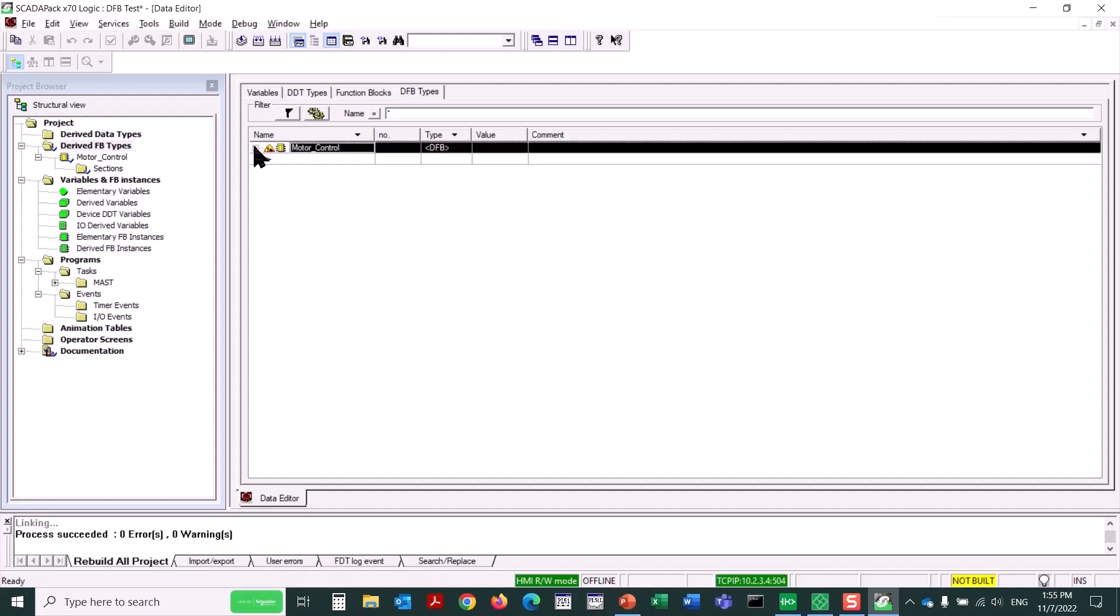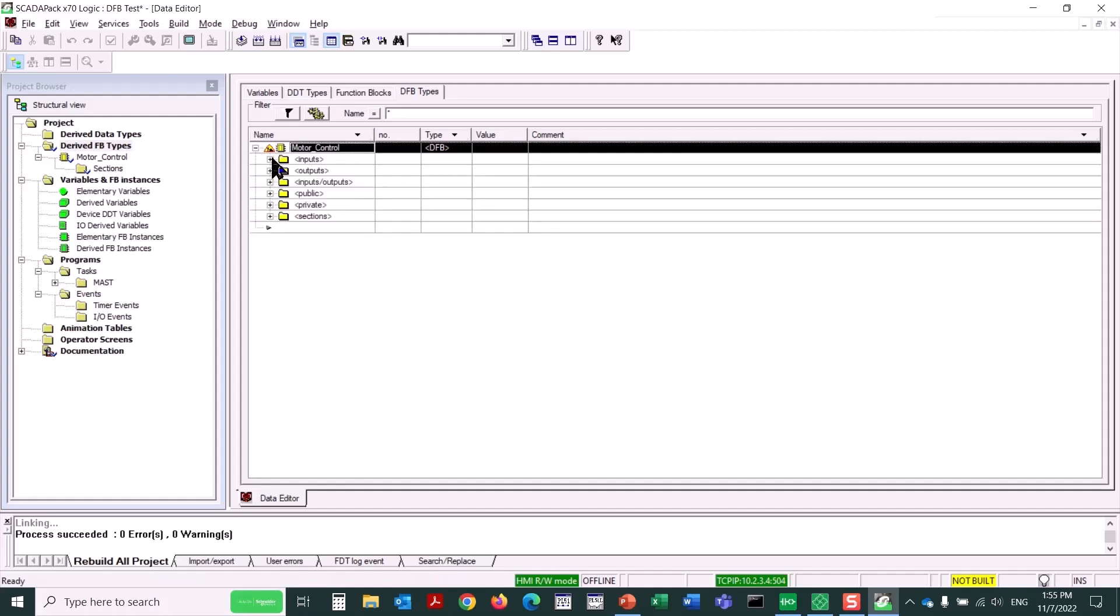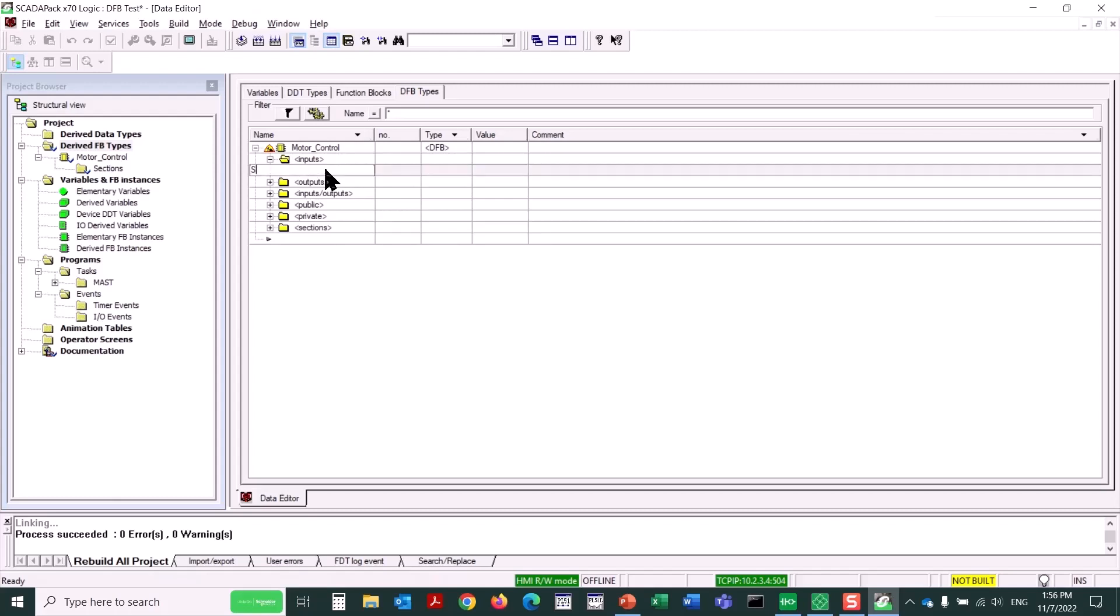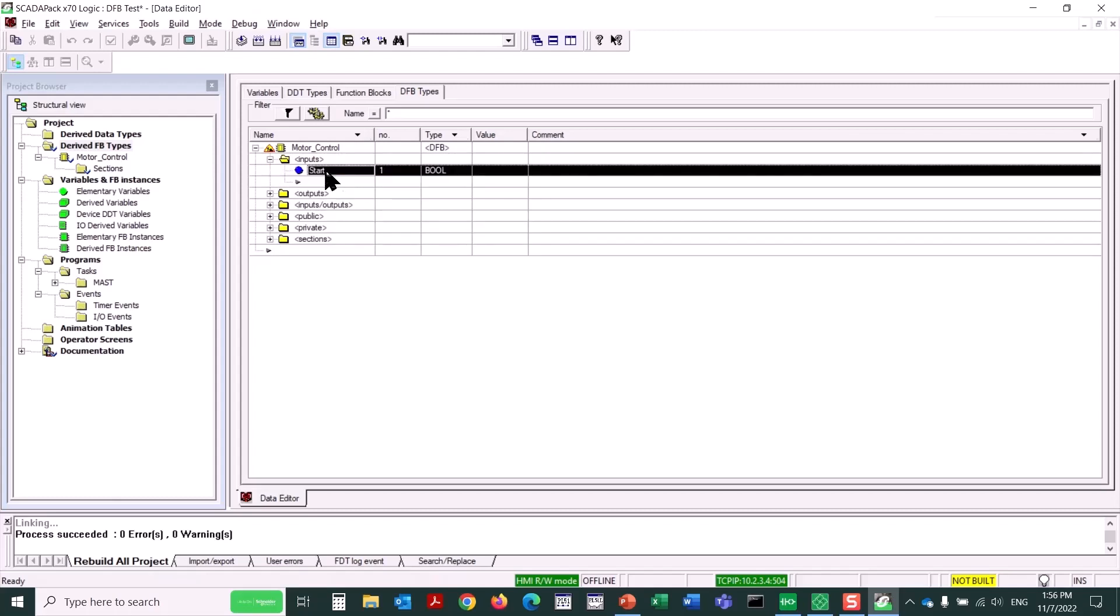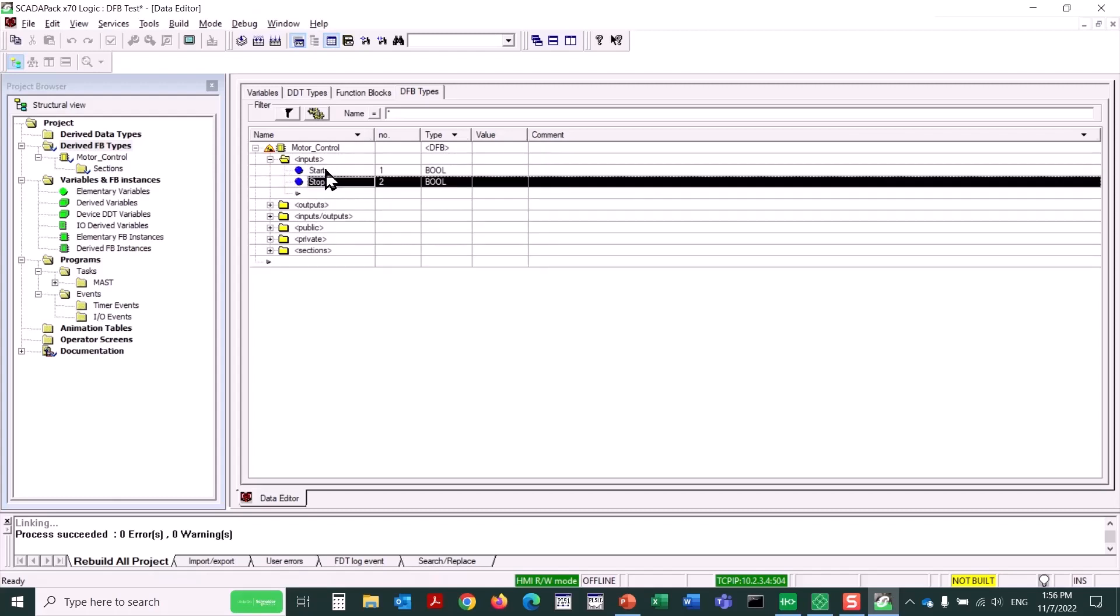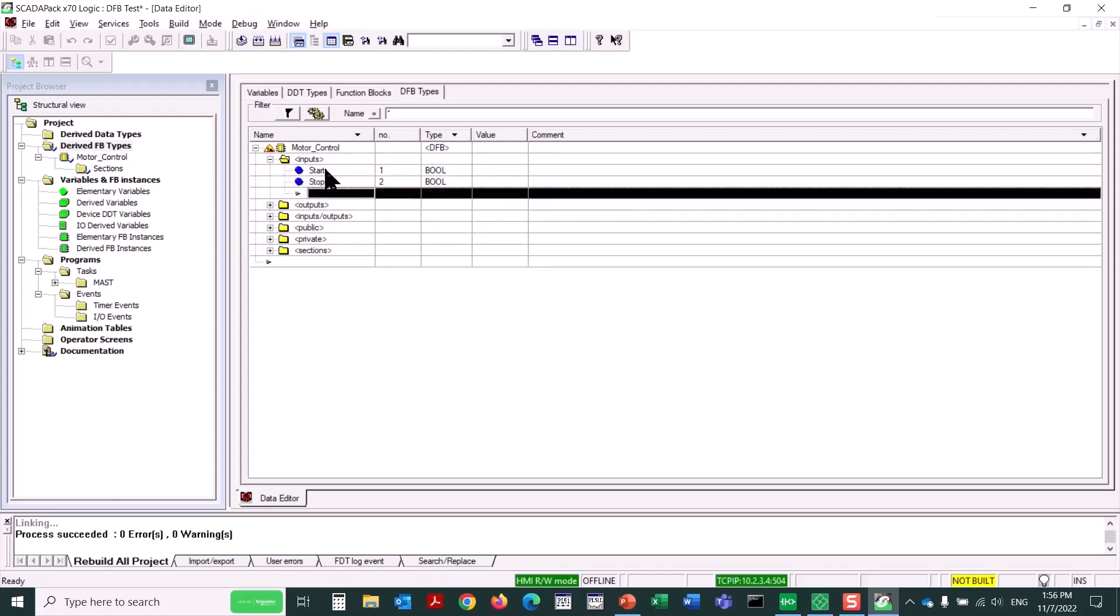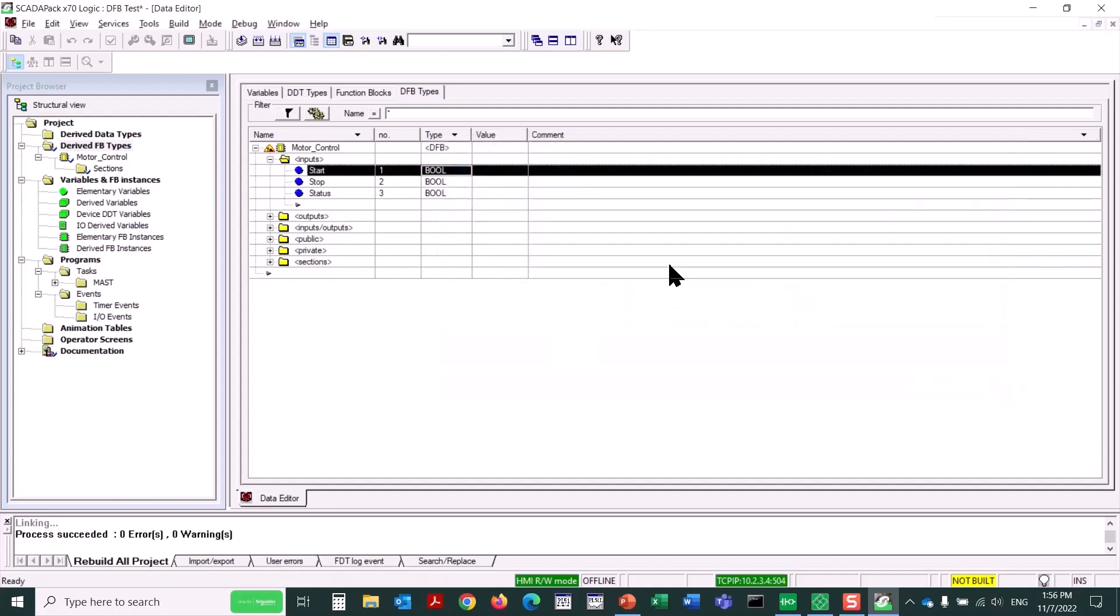We then expand the DFB, and we can see categories here, subfolders called Inputs, Outputs, Input Output, Public and Private variables, and then sections where logic is actually created. I'll expand the Inputs folder, and then add a few inputs. I'll add Start, Stop, and Status. You can see that each of these is by default created as a boolean type, but we can change those as required.